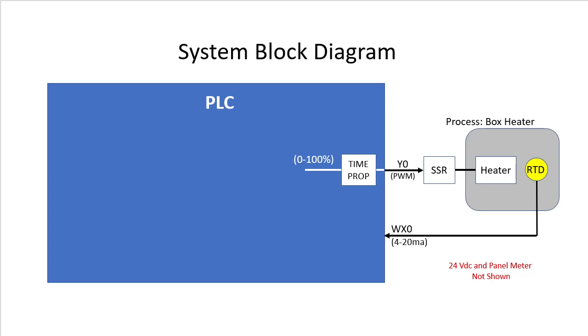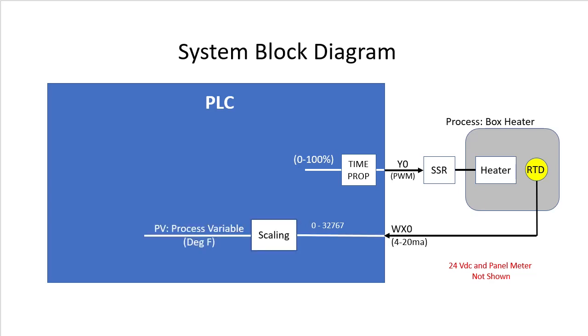Now we take that digitized signal which ranges from 0 to 32767 and scale it to degrees Fahrenheit. That's our process variable. It tells us what the current status of our process is. Why degrees Fahrenheit? Because we want to specify the desired temperature in degrees Fahrenheit. We call that the set point, which we will just manually set for this demo.